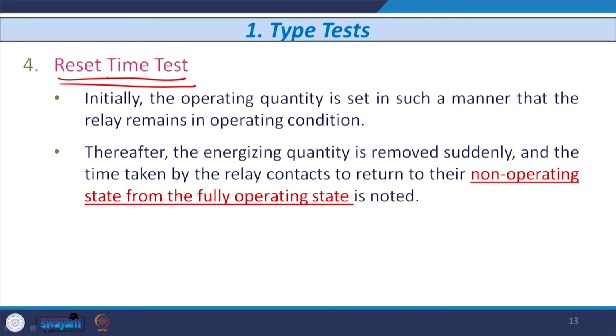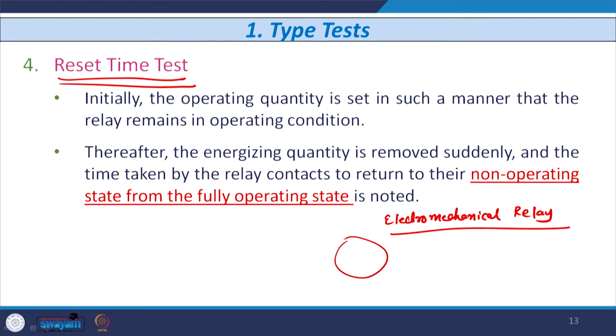In this reset time, if I consider, let us say, an electromechanical relay, and this is the disc of the relay, and it starts moving: a fault occurs, the relay operates, the disc starts moving, and after a certain travel the contacts of the relay operate. So, this is nothing but the operating time of the relay.